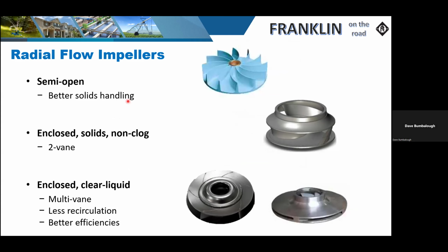We've got semi-open. You see a lot of these particular types used on fans or moving of air. If you were to look at an above ground motor, you can see this type where it's designed to move air and to push it across the motor to keep it cool. We also have this type in a pump, which in most cases you're not going to see unless you tear it apart. We do have some enclosed, which are a little larger design.